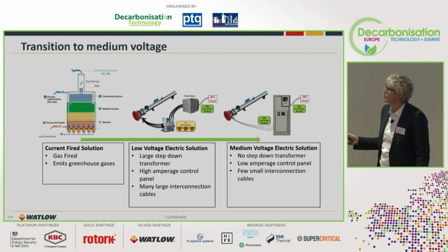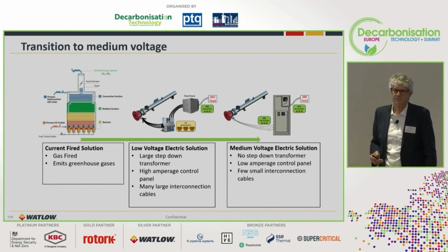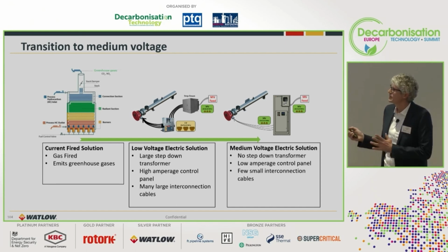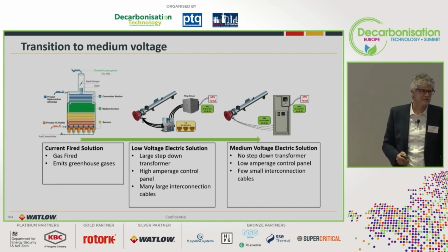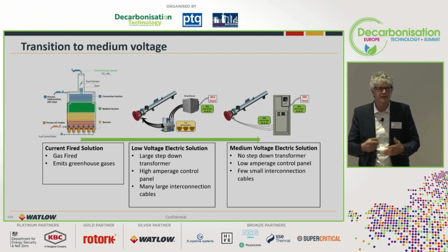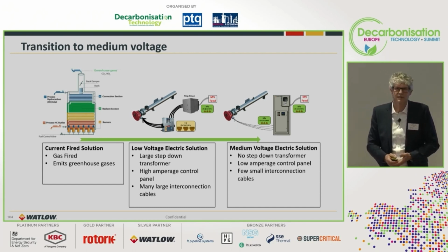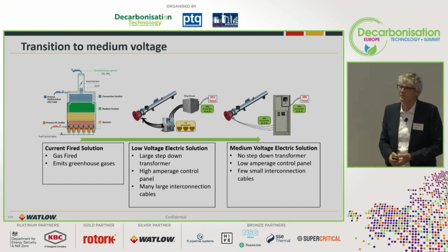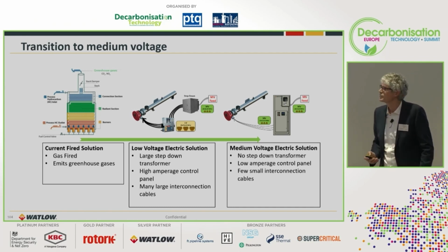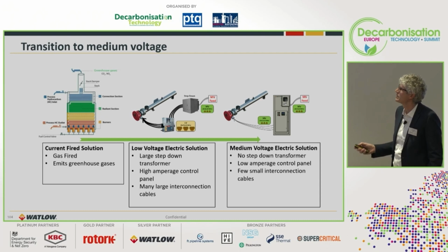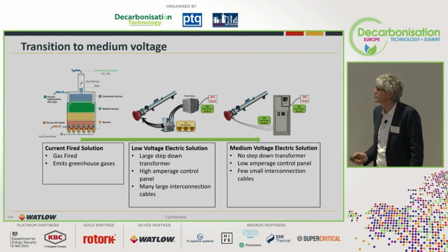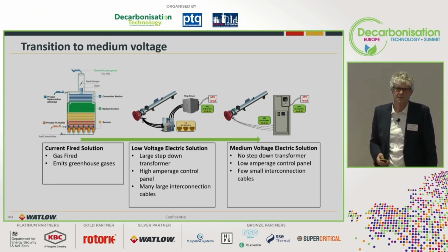We have a lot of very thick interconnection cables. A solution is we go to a medium voltage heater, which can operate. Currently we have one at 4,160 volts, which can be operated directly with that voltage. And we are developing one up to 7.2 kilovolt, coming by the end of the year. So we can reduce the step-down transformer, or sometimes avoid it, and we certainly save cost on the interconnection.